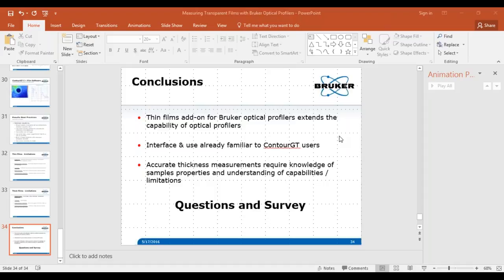If using thick film mode at say 8 microns, can you see the topography of the bottom of the film? Yes, you should have no problem getting the lower surface with thick film. You'll get two independent surfaces that you can then process as you choose.